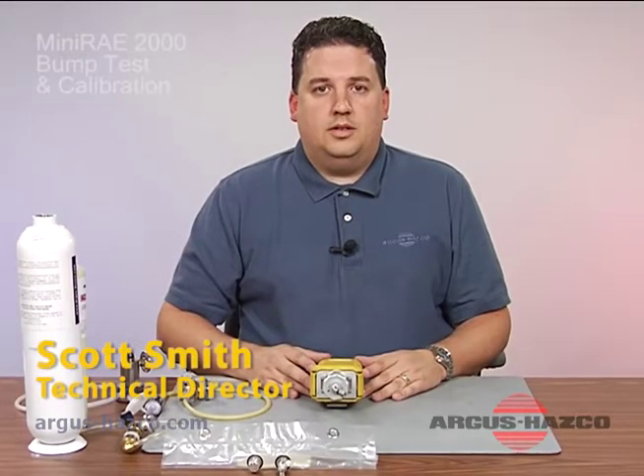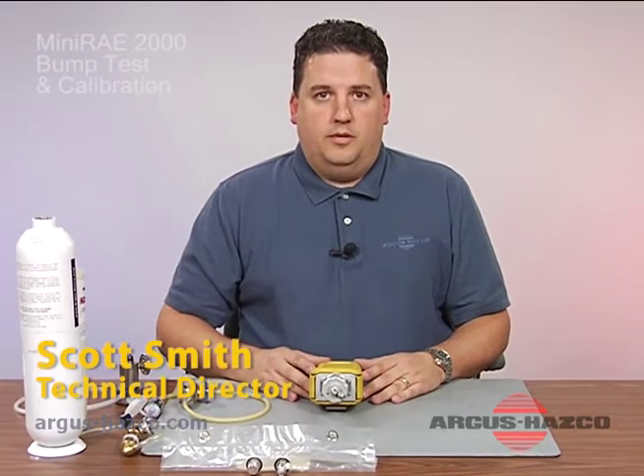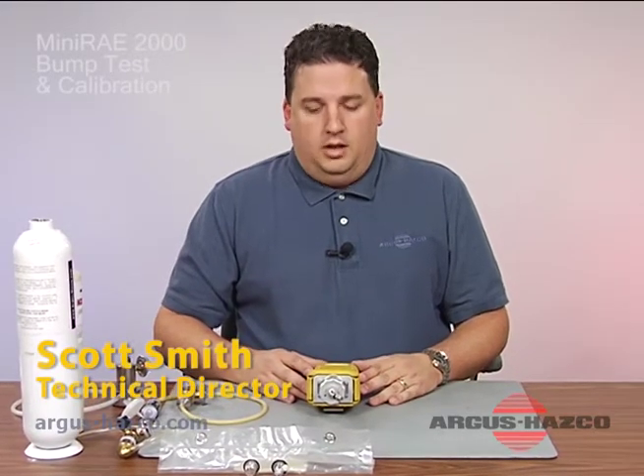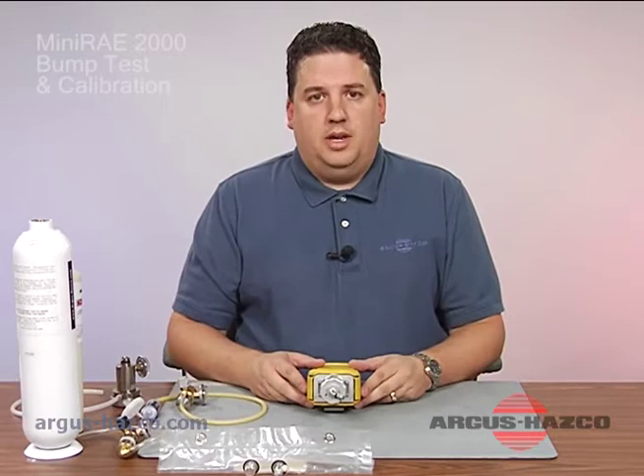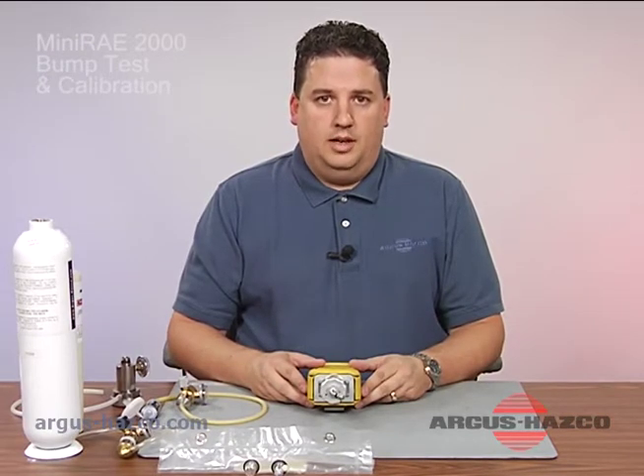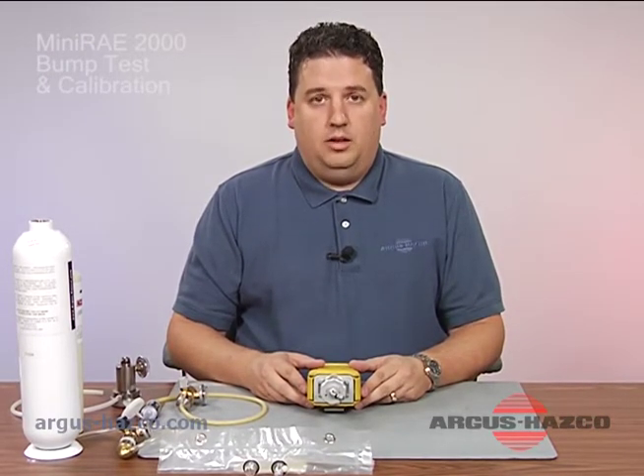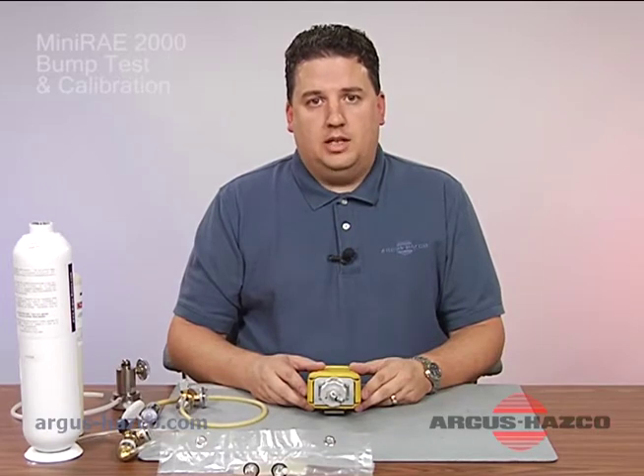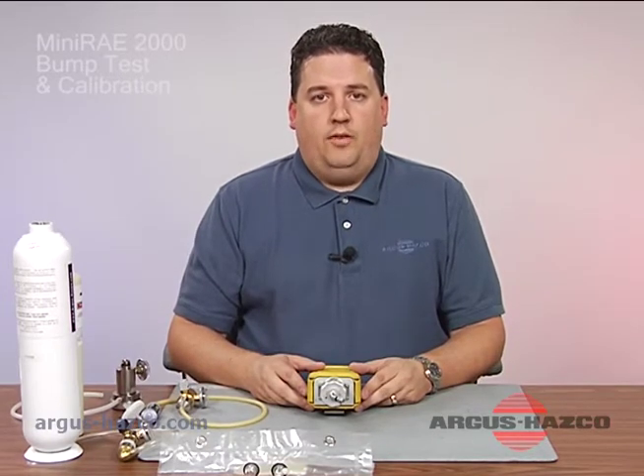Today we're going to discuss bump test and calibration of a MiniRAE 2000. A lot of people confuse bump testing with calibration, thinking they're one and the same. In essence, if a unit is calibrated and you simply apply calibration gas with a known concentration and it falls within a specific tolerance, there's no need for calibration because it has passed the bump test.